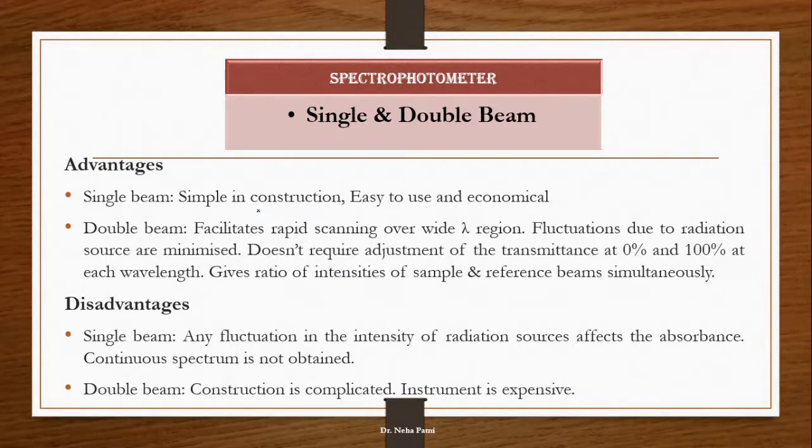Advantages of double beam: it facilitates rapid scanning over wide wavelength region, fluctuations are minimized, and it gives the ratio of intensity of sample and reference simultaneously. Disadvantages: single beam has many fluctuations that will affect the absorbance, and you don't get continuous spectrum. Double beam is quite complicated and expensive, while single beam was simple and quite cheap. This is what you can say about spectrophotometer.